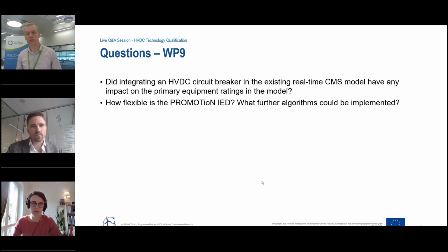We've used a configuration assuming a substation with 3 outgoing links, with voltage and current measurements on both poles, positive and negative, and the bus bar. None of those types of stations are available out in the field today, so I can't comment on that. But what would be necessary for the IED to operate is voltage and current measurements at 50 kilohertz. This is what we tested, at least, from all cable ends and the bus bar, both poles.